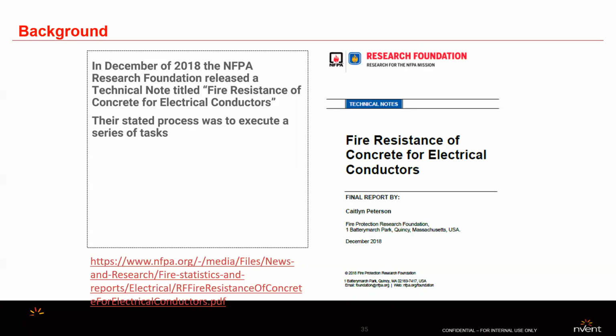where that backed this up. And because NFPA also publishes the NEC, we are expecting the next code cycle for the NFPA to up its requirement to 4 or maybe 5 inches of concrete, up from the present 2 inches of concrete, because now it's pretty obvious that 2 inches of concrete will not give you the protection that you need. If anyone likes, we do have this white paper available.